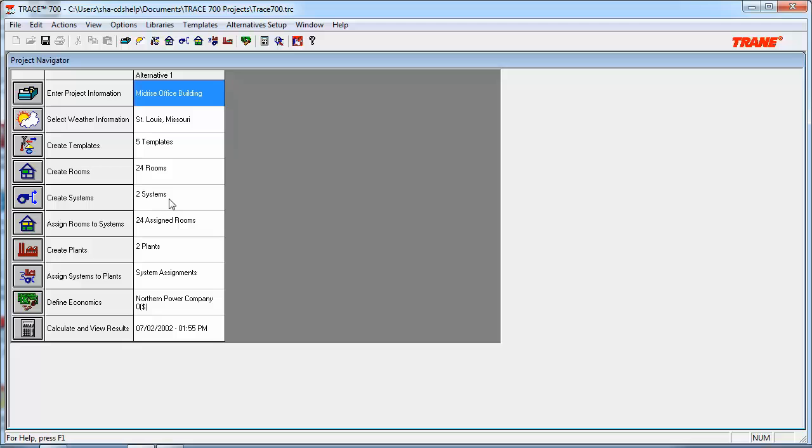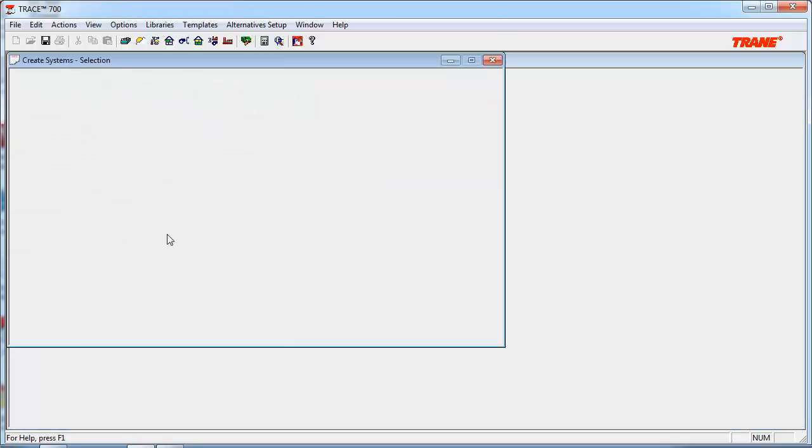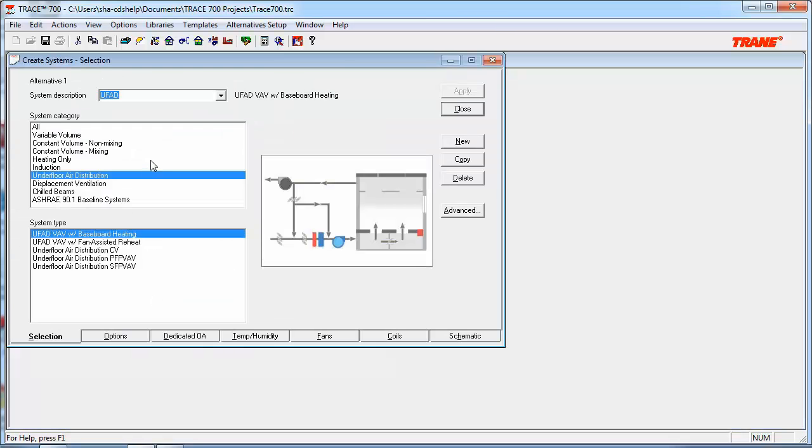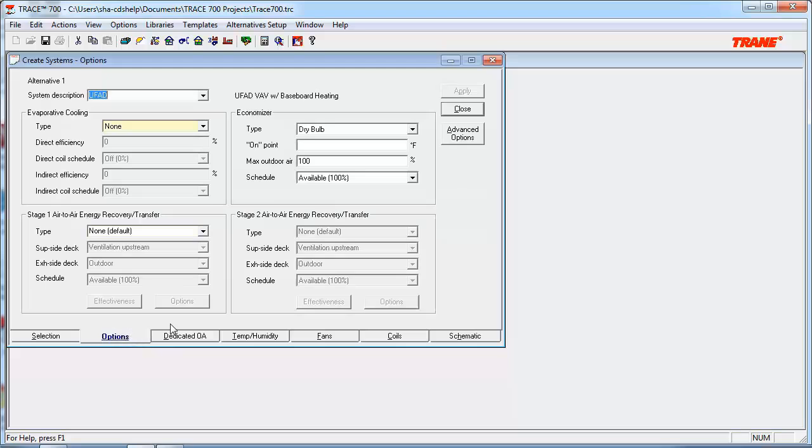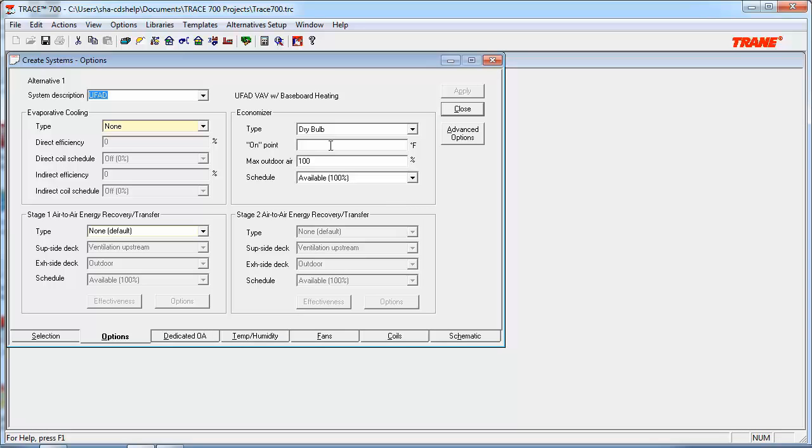Assuming we have a project created, let's start with the Options tab in Create Systems. So we'll open up Create Systems and click on the Options tab. This tab is where you define several different parameters, but what we're going to focus on today is the Economizer. By leaving the input blank for the on point, TRACE will use the design supply temperature as the control point for the Economizer. Since UFAD systems typically have higher supply temperatures than conventional systems, this can mean a higher rate of Economizer operation, which may reduce mechanical cooling.